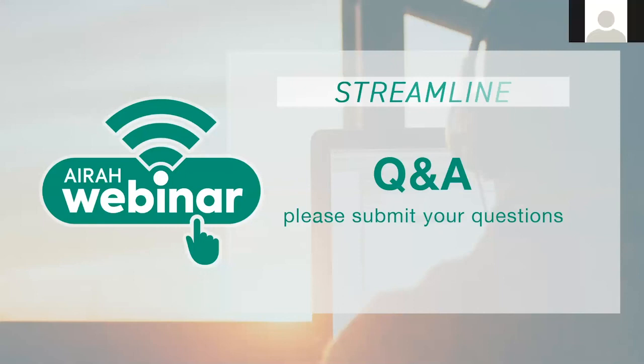Thanks, Grace. Just another one there from Matthew, who's asking, does Section J take into account the Pumps Australia standard, whereby they have a plus or minus 10% on the flow? So the example that I've used there already accounts for typical safety margins that will apply for fouling in a system, for example. And it also already accounts for your plus and minus flows.